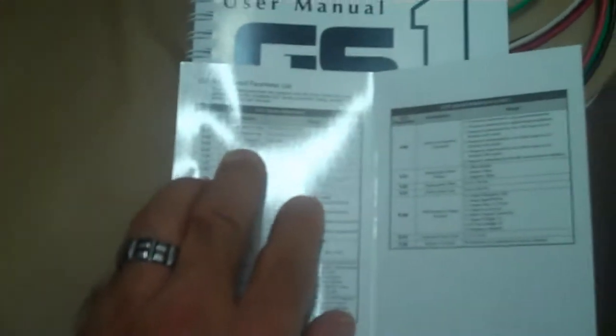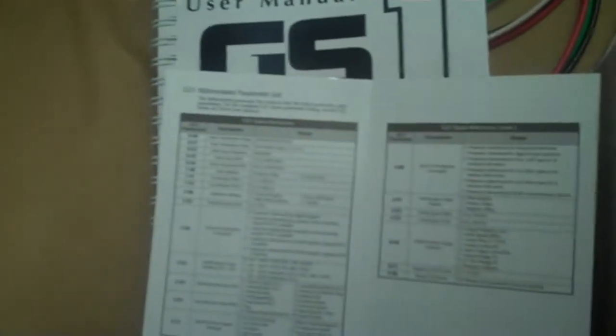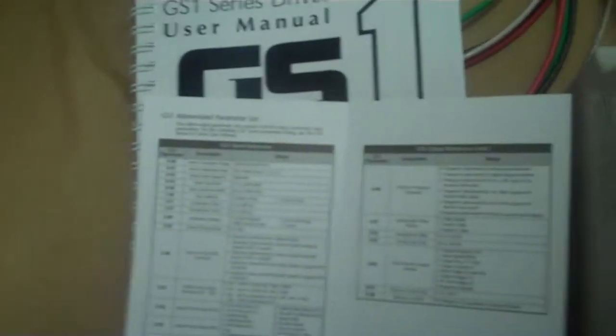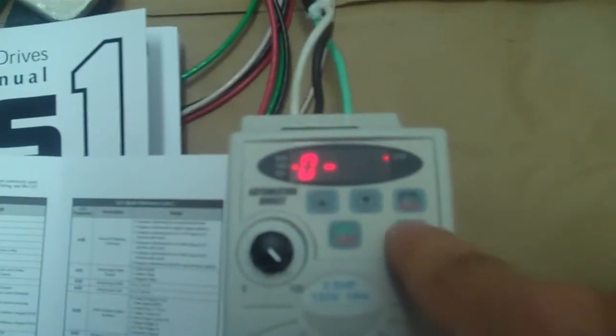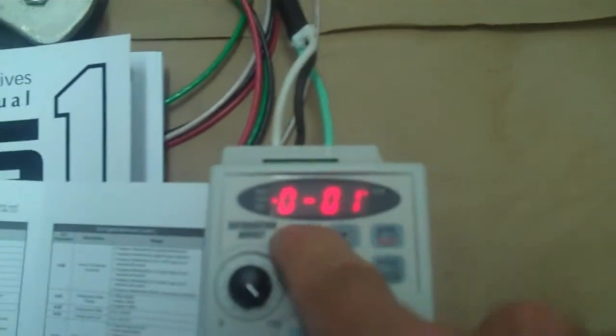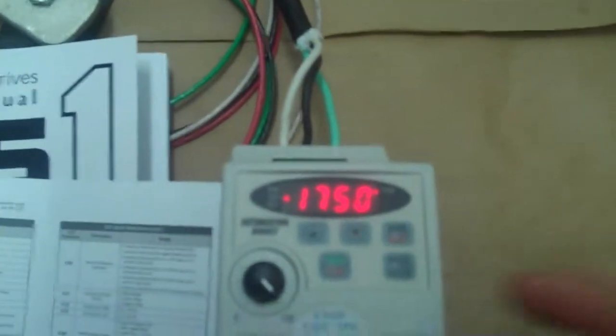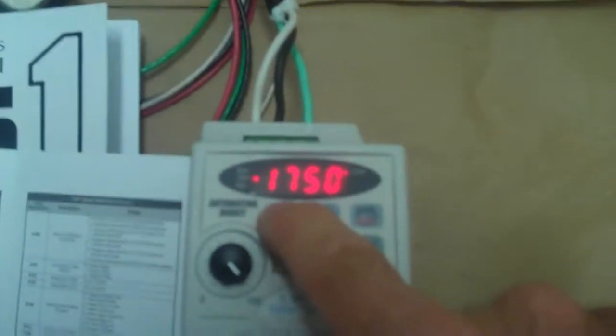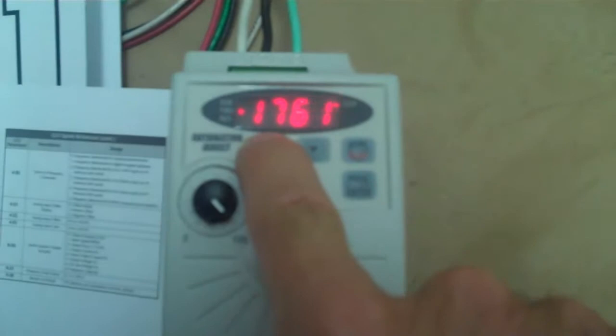Let's get going with the programming. Basically we're going to program the zero parameters, those are all the motor parameters. The first one here that's of interest to us is motor base RPM. That's zero dash zero three and the motor base RPM for this motor is 3450. I'm going to push program, zero, program again, and then three. It says 1750 so that's clearly not 3450 so we're going to make that happen.